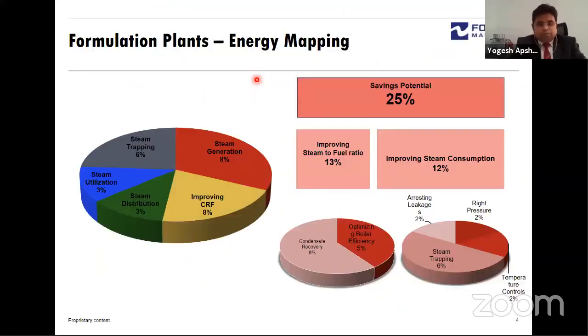So let's go ahead. This is our typical analysis of the formulation plants. What are the gaps in the formulation plants as far as energy mapping is concerned? Based on our extensive analysis and survey of more than 1,000 pharma plants across the Middle East, North Africa, India, and Southeast Asia, we have come to this very important slide, where we show a savings potential of almost 25% in any pharmaceutical company. This 25% of savings comes from two aspects. One is improving the steam to fuel ratio, which has to do with condensate recovery and boiler house improvement. Condensate recovery can contribute 8% of the savings, and optimizing the efficiency 5%.